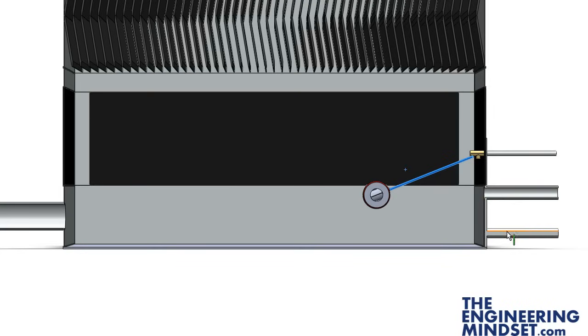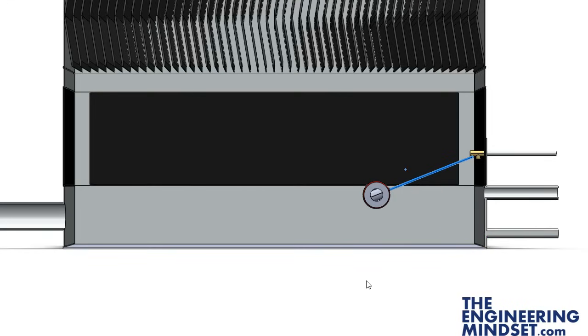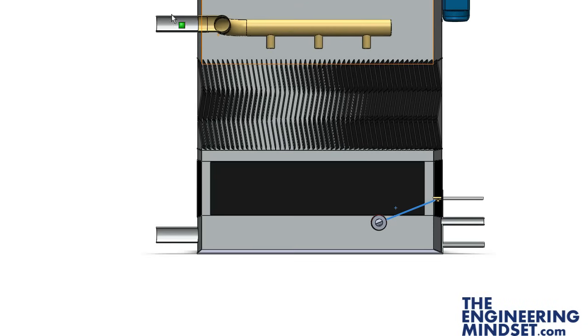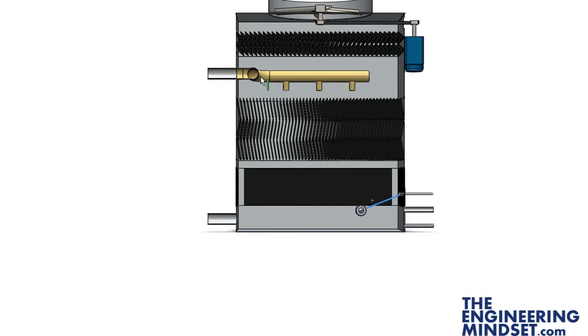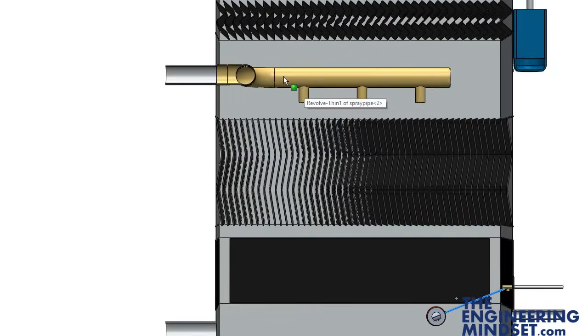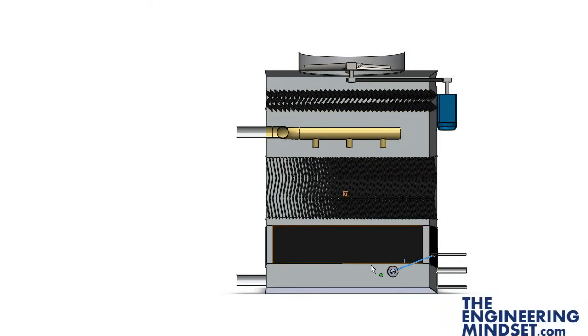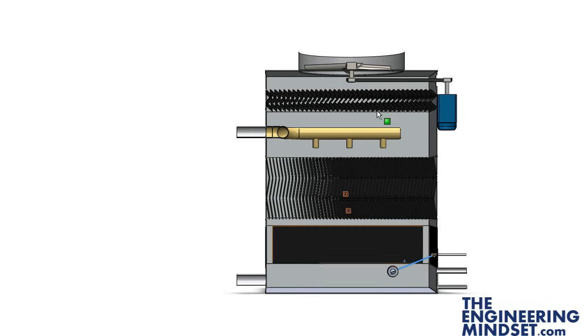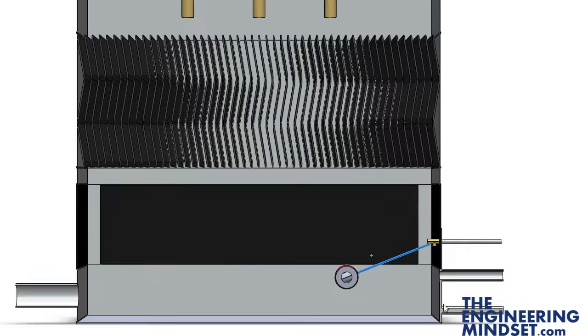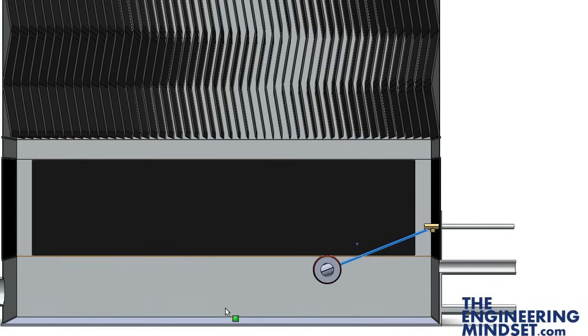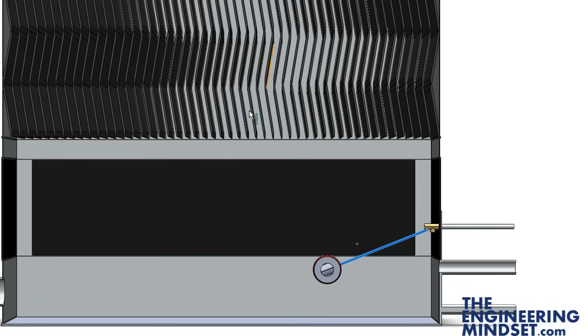And then the last part here we've got is the drain. The drain is quite important because the water that's entering this tower here contains salts and bacteria and stuff like that. As this water evaporates it's going to leave behind that salt and the gunk and muck that's contained within the water. That salt won't evaporate. That will start to collect up here in the basin or up on the fill packaging. So once it reaches a certain level...